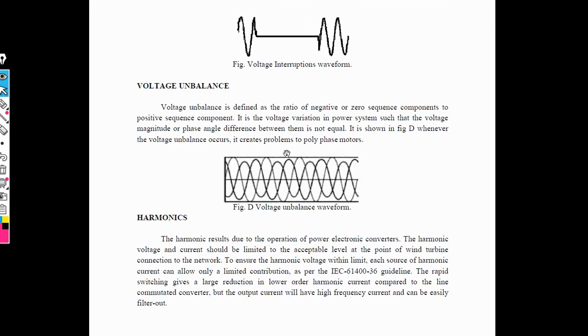Then unbalanced voltage. Voltage unbalance is the ratio of the negative sequence component and the positive sequence component. That means in voltage unbalance we have to study three components: zero sequence component, positive sequence component and negative sequence component. This is the three-phase diagram, and the voltage will be unbalanced. That means R, Y and B three-phase voltage will be unbalanced. The upper axis is called the positive sequence component. Then this is the negative sequence component and this is the zero sequence component.